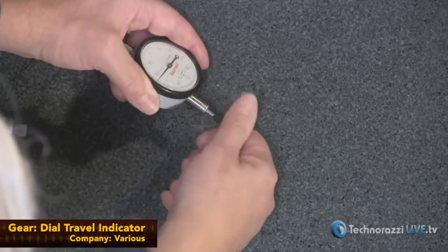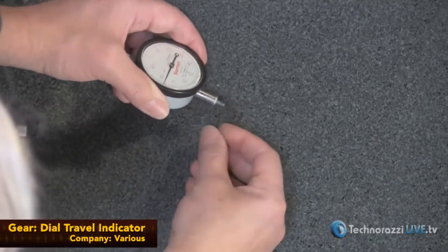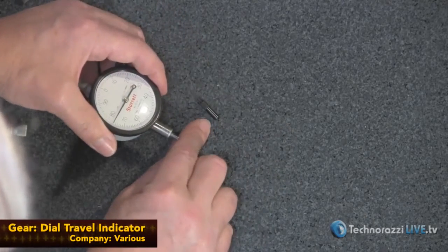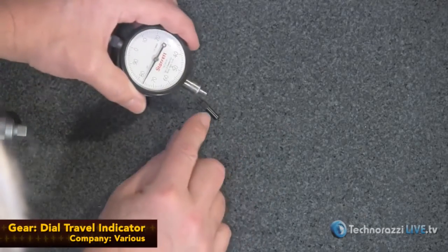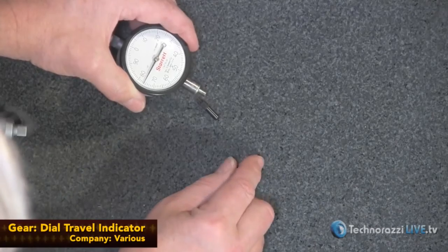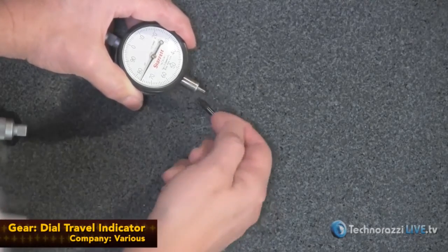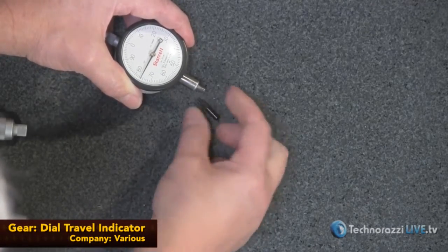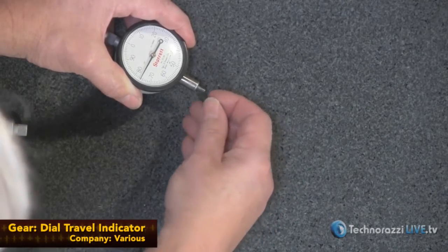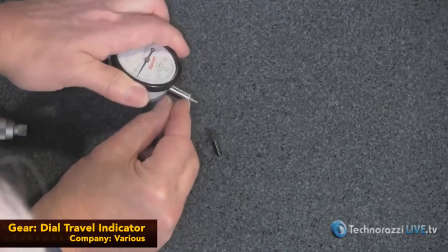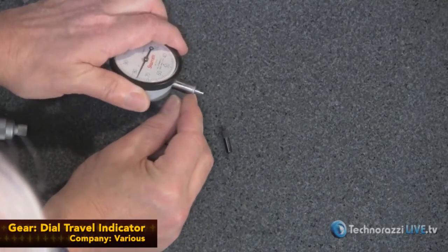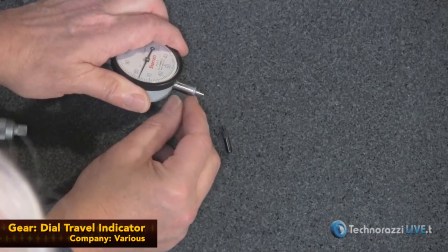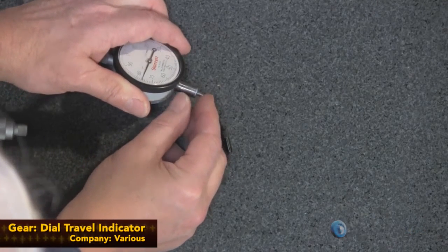These also, as any indicator, have a removable measuring tip they call the contact point. They come in different lengths, and on these, length doesn't matter. You can use any length because it's measuring straight up and down in the same direction. We always look right in this area for a large buildup of dirt or crust because that's going to affect things. Make sure it returns.